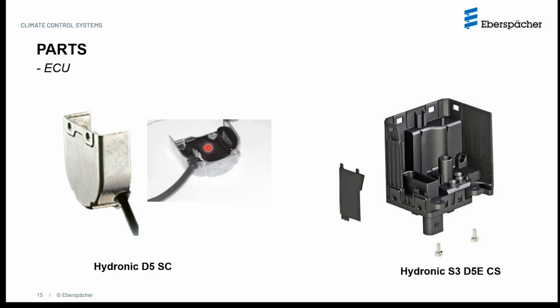The chances of an ECU going bad is very, very slim. Please do not start off your diagnostics and repairs by replacing an ECU, because that's not how it should be done. As I mentioned, you have to go through the diagnostic process, and if you do have an ECU fault code, of course, you should replace the ECU. I'm not suggesting that the ECU never fails. There could be times when the ECU may fail, but then you have to make sure that it is an ECU failure. The ECUs are the most expensive part of the whole heater assembly.